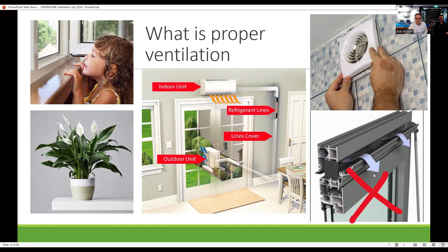This idea of positive pressure, sucking air from the ceiling, that's just crazy. It might have worked in the past in older, really air-leaky homes, but we shouldn't be doing that as homes become more airtight. It just won't work because the air has got to escape from somewhere. And negative pressure isn't going to work either, that's going to suck in contaminants through the gaps, probably from the roof space, and there's a lot of nasty stuff up there. The biggest thing is it's just going to dump all the warm air out that you've paid to heat. So that's not a good thing either.